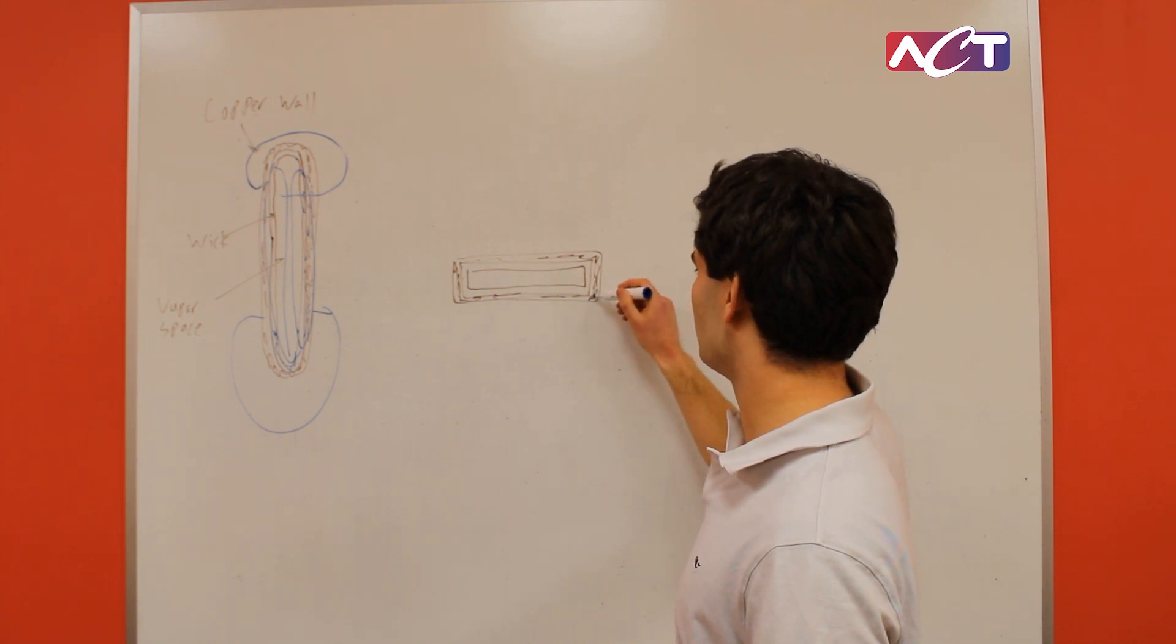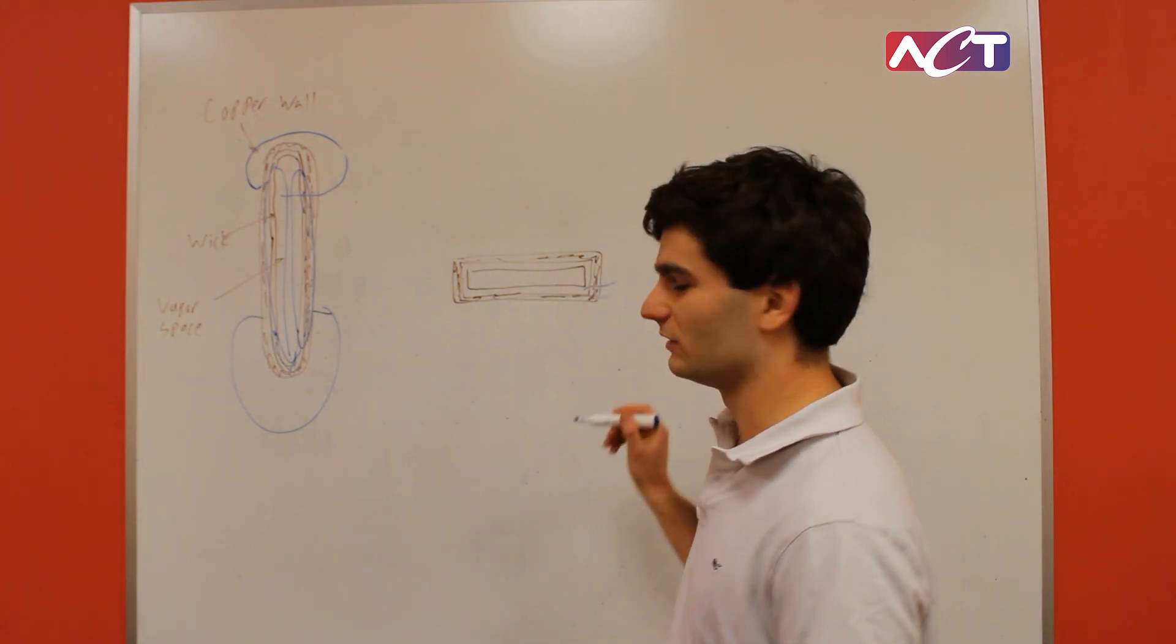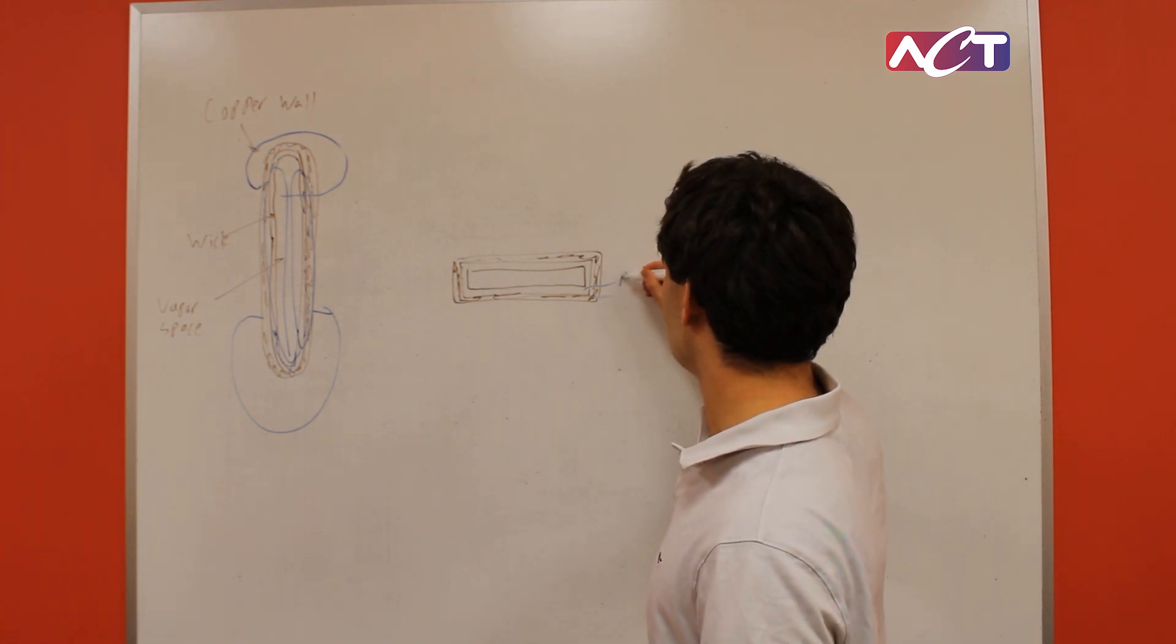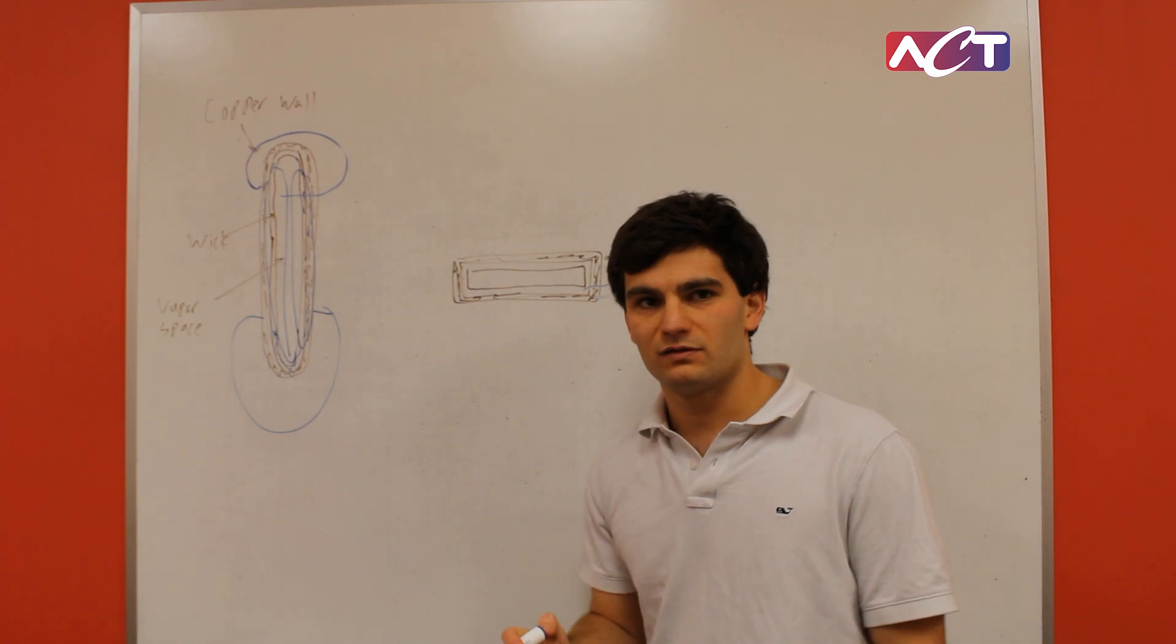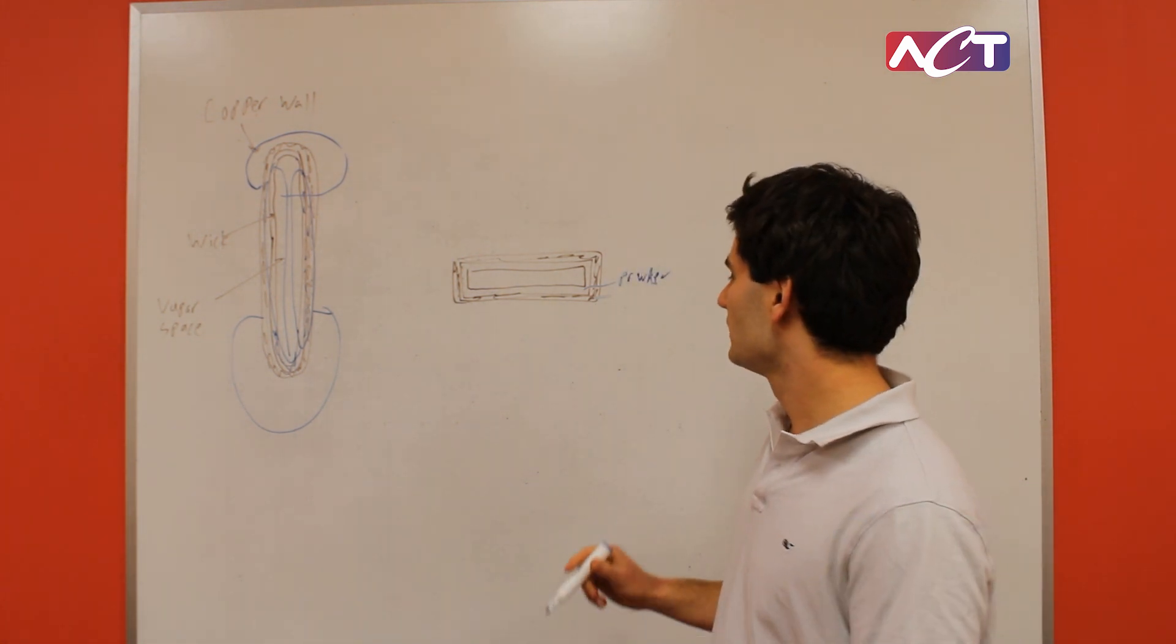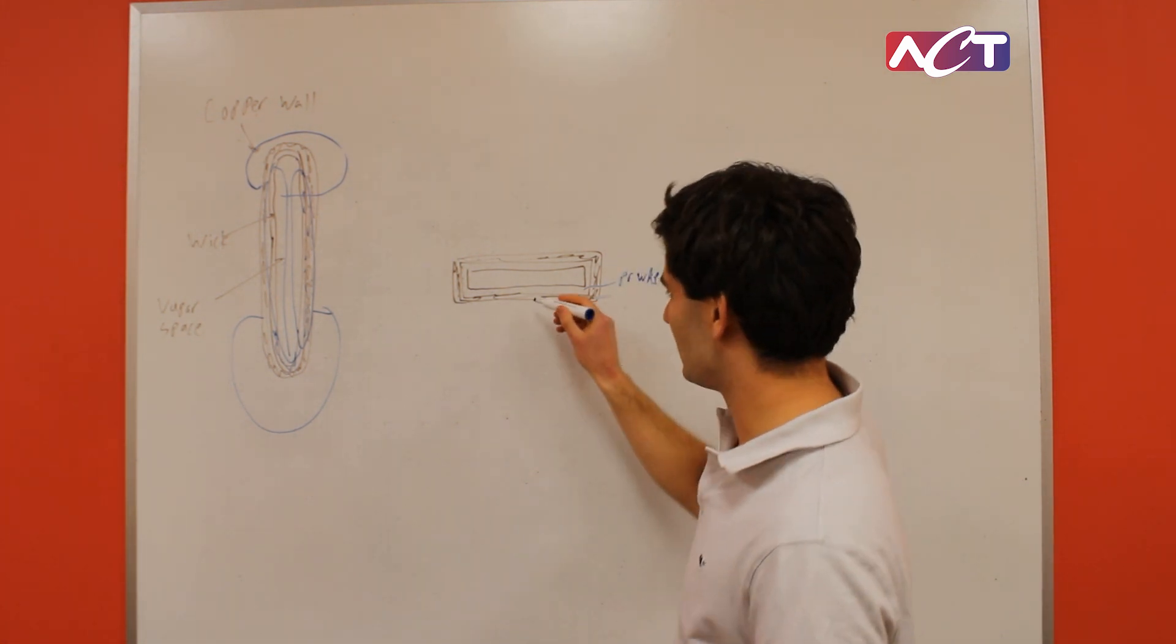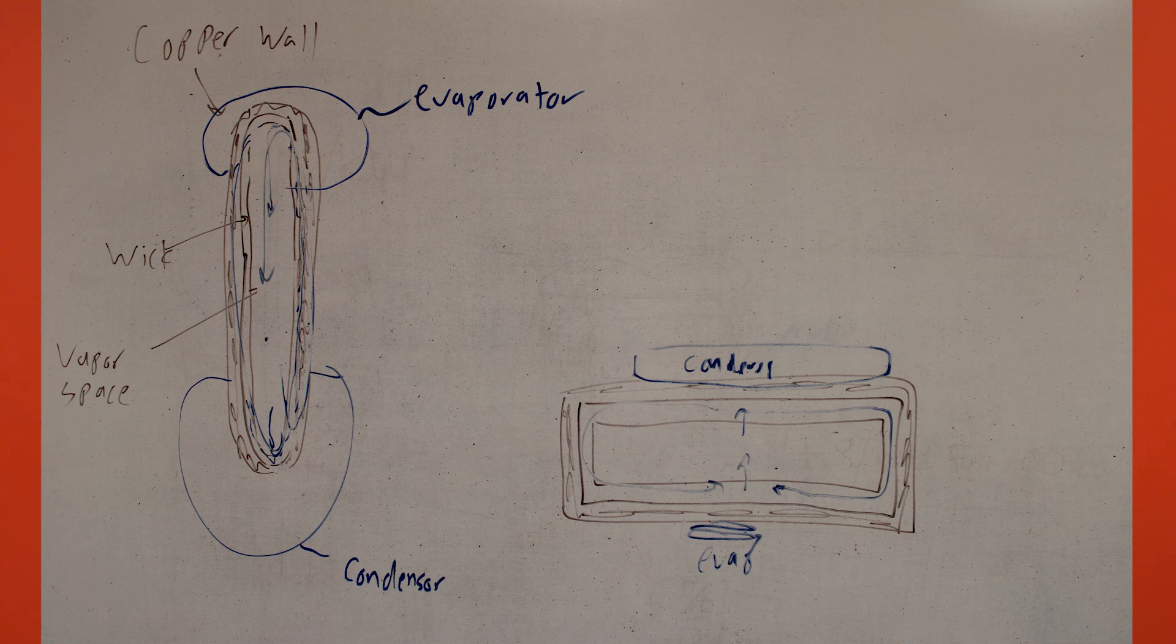We have a copper wall, and then you have some sort of wick. Typically the wick is going to be some sort of powder wick since the screen doesn't really work as well for this geometry here. Same exact idea, you have some sort of evaporator, some sort of condenser.